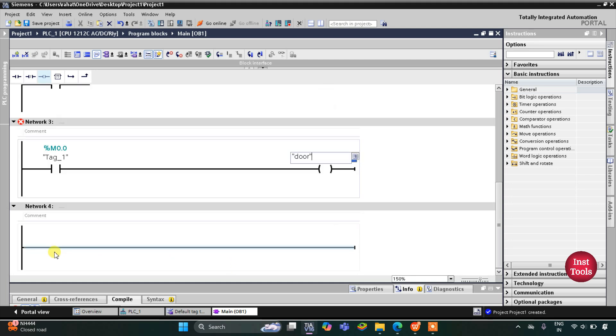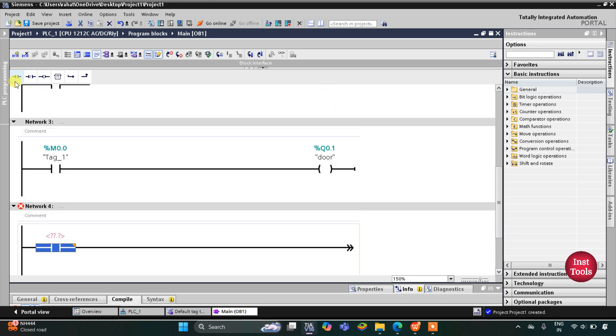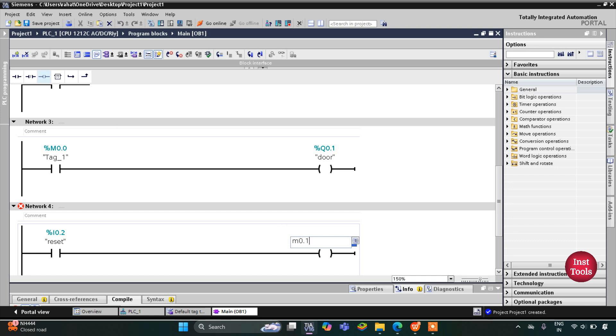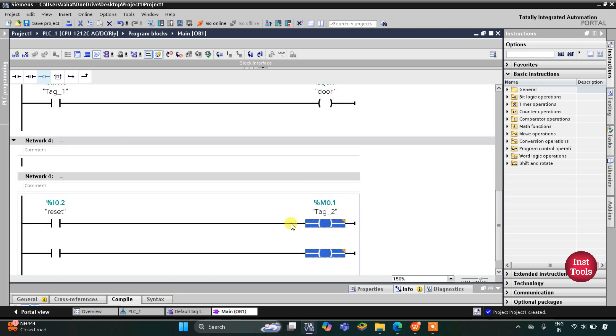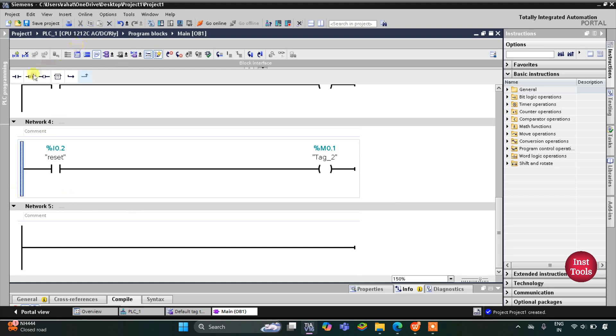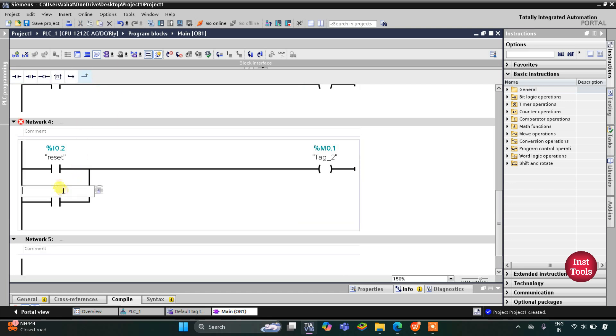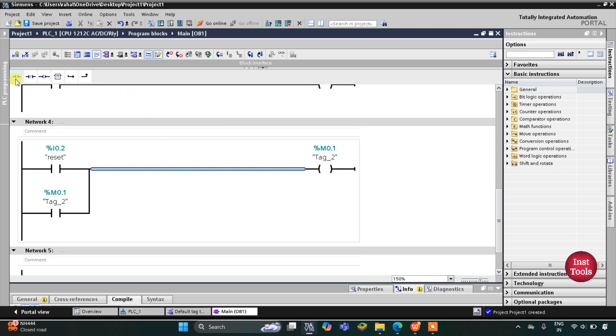We also have the reset button input. I will insert a normally open contact for the reset button and a coil for memory bit M0.1. I will latch M0.1 by opening a branch, adding a normally open contact for M0.1, and then closing. This M0.1 will be used as a normally closed contact with address M0.1 to clear the emergency state.